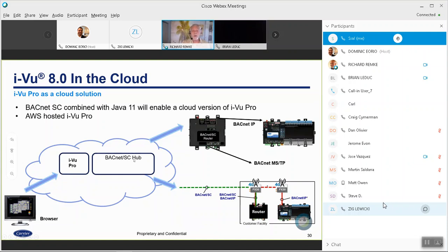The Pro would talk side by side with a BACnet Secure Connect hub, also in the cloud, and that would enable you to communicate to items on site, whether that is to a BACnet SC router again, or a BACnet SC enabled cell modem. So those are items that we will do, and one of the reasons we can start looking at this, besides the fact that ASHRAE just came out with a spec at the end in December 2019, is that Java 11 helps us enable this in the cloud, because Java 11 allows us to separate out portions of the application.